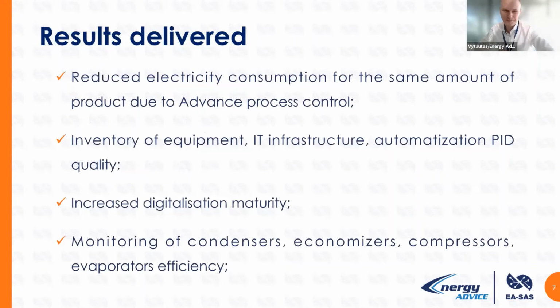What results do we deliver? In fact, we reduce electricity consumption through advanced process control. Of course, we do an inventory of your equipment, IT infrastructure, and your PID regulators, and what is inside them. So the digital twin catches everything, all the problems you have. Sometimes you may not know of these problems. Of course, it increases digitalization maturity, and we monitor not only the consumer side, how the cooling energy is consumed, but also the efficiencies of condensers, economizers, compressors and evaporators. It's also important because deterioration of efficiencies would lead to decreased overall efficiency of a system and increased electricity consumption.